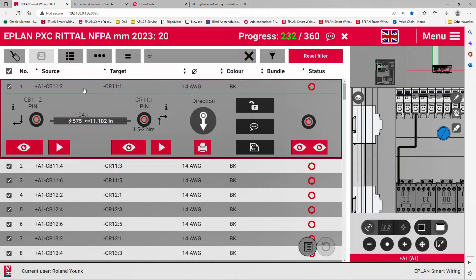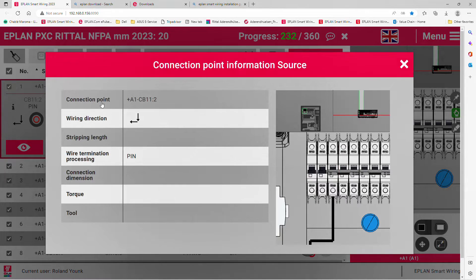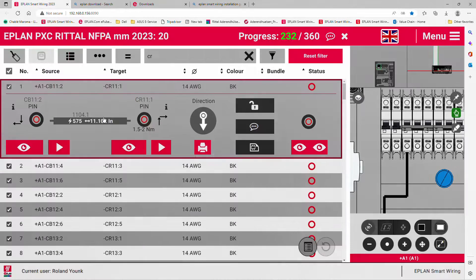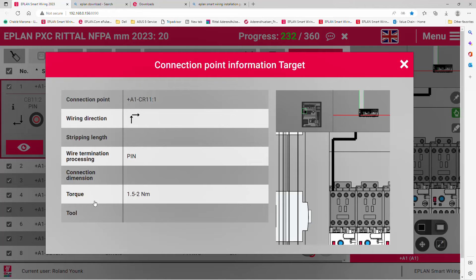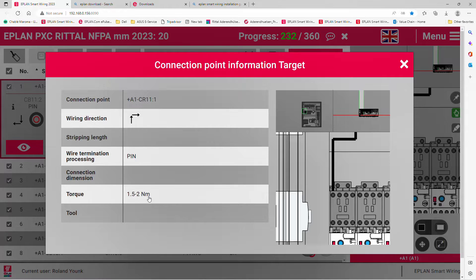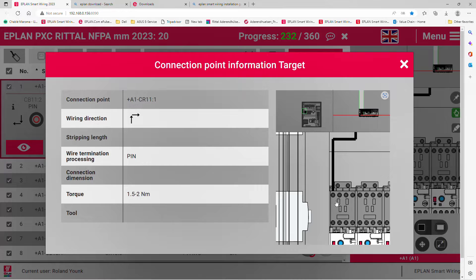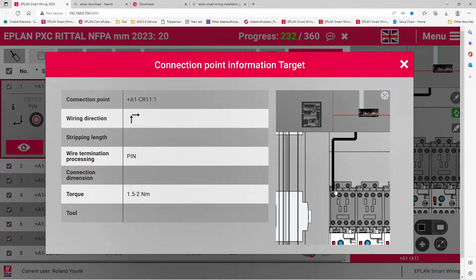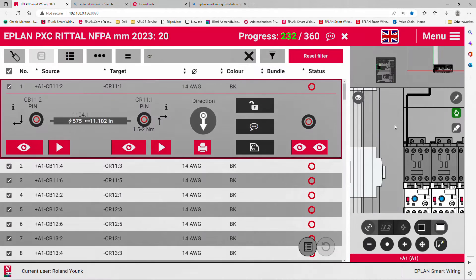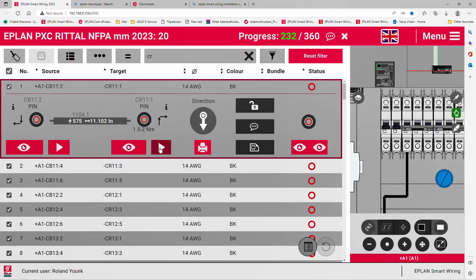Every single device has a source with information and a target with information. You can even specify the torque range of the screw. For your screwdriver, you can specify a special tool. From this particular pin that you can see visually, you go to the top and move over to the right. That's how the wiring goes from this device to the next device.